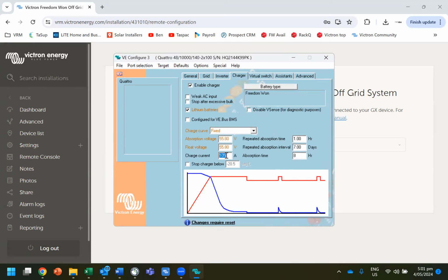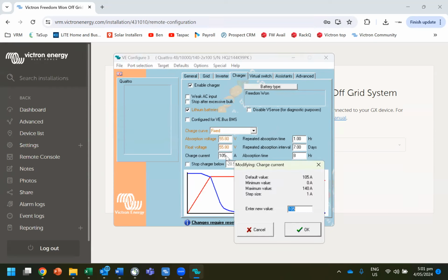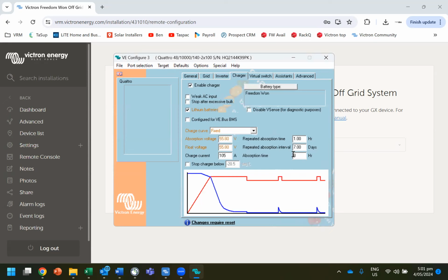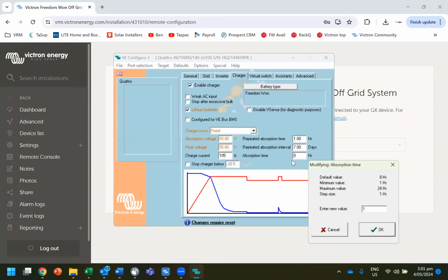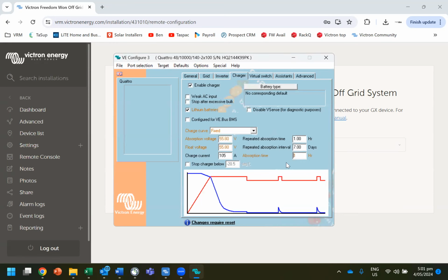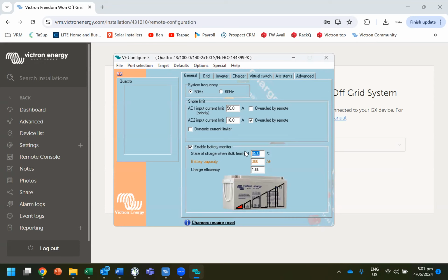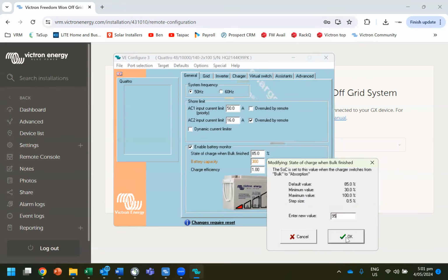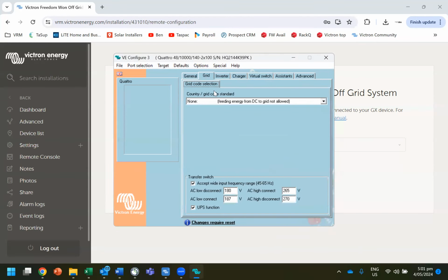If the battery can handle the full charging current of the inverter, great. Leave it at normal, at default. And normally I would change the absorption time to 1 hour. Okay. So now this is an old type, so I'm going to go back to 95% here. Just bear with me.